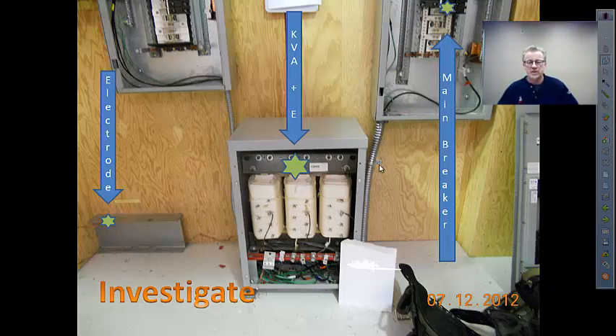The protection from short circuit and ground fault is really not so much protection as a limitation of risk. By limiting the length of conductor to either 10 or 25 foot if it's inside of the building typically, and having stipulations about a percentage of ampacity of the conductor to the upstream device multiplied by the transformer turns ratio, and also by requiring the conductors to be protected from physical damage, we're limiting the risk of short circuit and ground fault, and then this breaker on the load side is only protecting for overload.